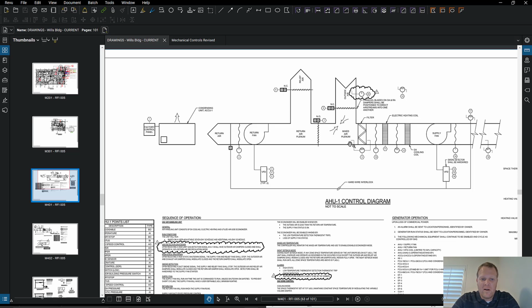If you just say, when are you going to start the motor or start the air handler, they're going to interpret that as the startup checklist. And the startup checklist, going back to the manufacturer, is going to say, okay, do something to make sure that this fan is running in the right direction, operate all the motorized dampers, make sure that they're functioning correctly. So you're going to have all these little checklists associated with this, and that's the startup. But that doesn't mean that the air handler is functioning.